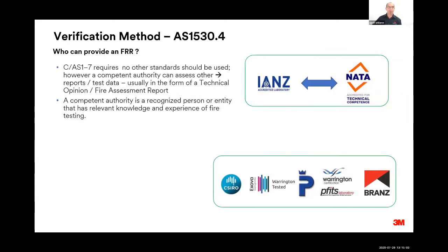So who can provide a fire resistance rating? Well, the requirement is that only those two standards are used, and a test report from an accredited lab is required for that. However, other data can be used from other tests, but that needs to be assessed through an accredited laboratory to be able to create an opinion or a fire assessment report. And a competent authority is someone that has the relevant knowledge and experience of fire testing.